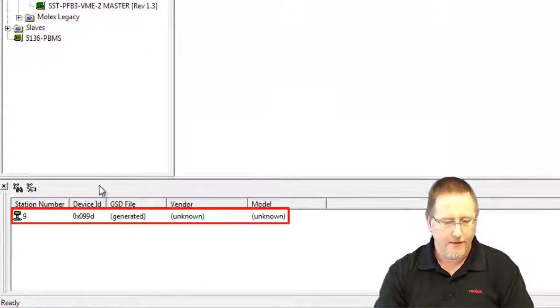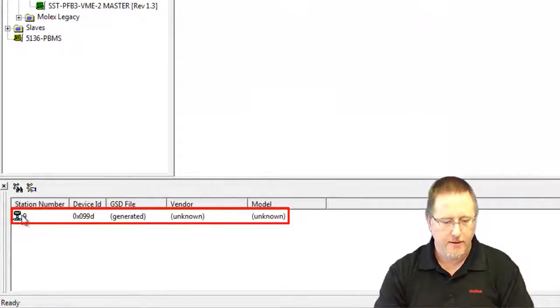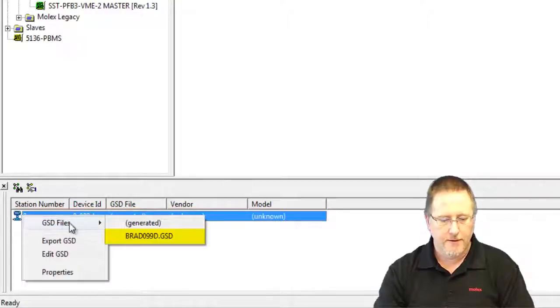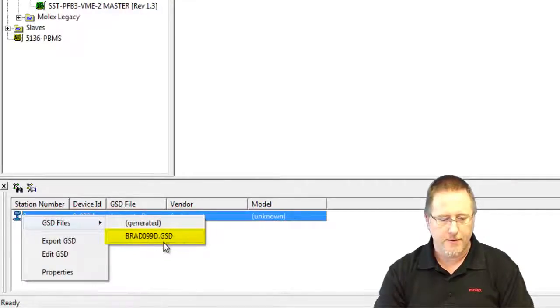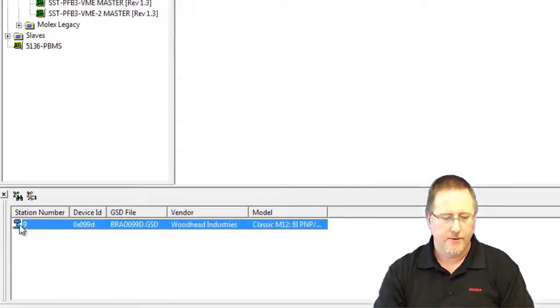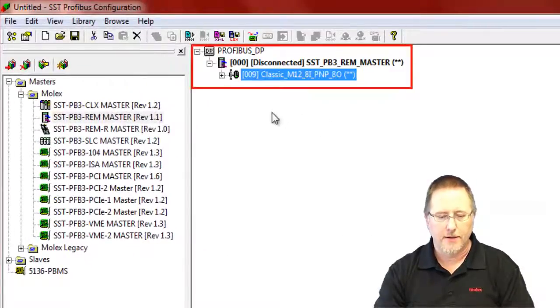And then we find our device. It's station number 9. We right click on it, select GSD file and select the proper manufacturer GSD file. And then we can drag that up and add it to the configuration.